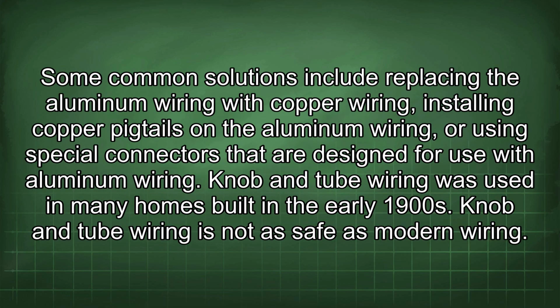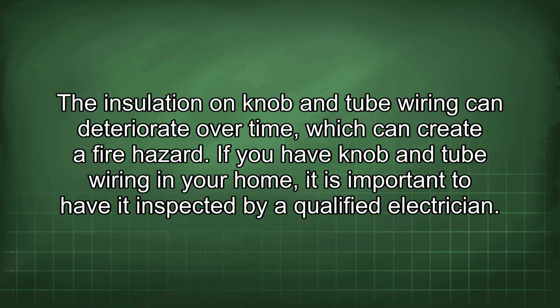Some common solutions include replacing the aluminum wiring with copper wiring, installing copper pigtails in the aluminum wiring, or using special connectors that are designed for use with aluminum wiring. Knob and tube wiring was used in many homes built in the early 1900s. Knob and tube wiring is not as safe as modern wiring. The insulation on knob and tube wiring can deteriorate over time, which can create a fire hazard.